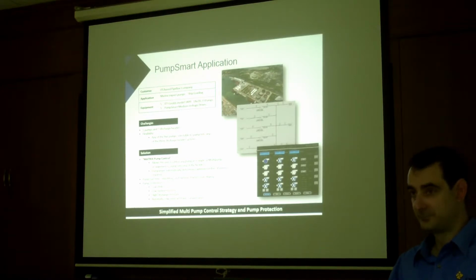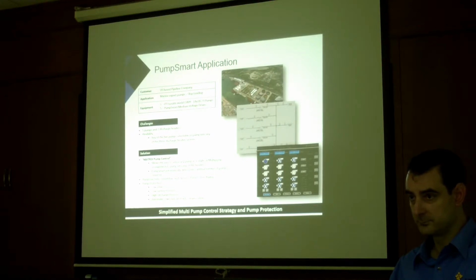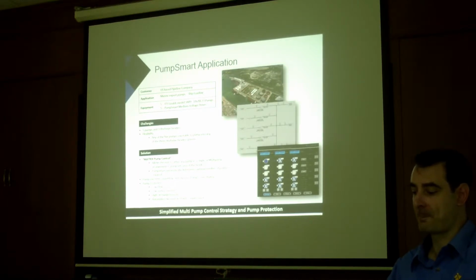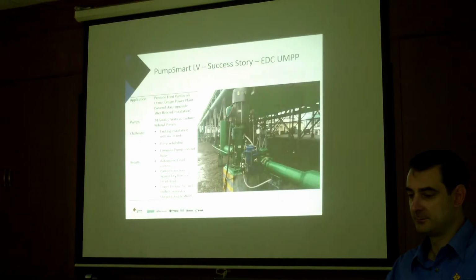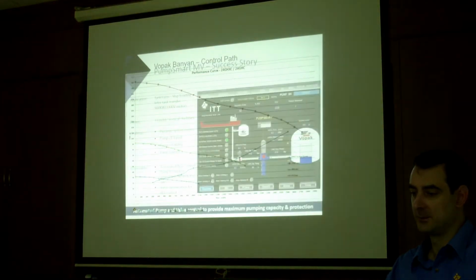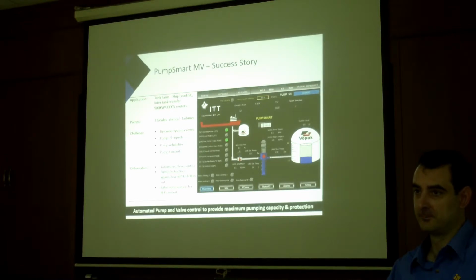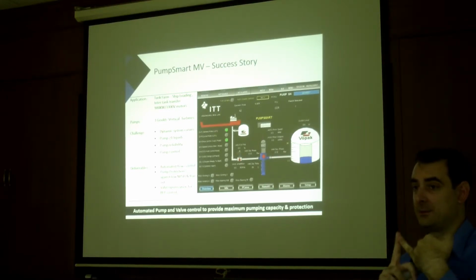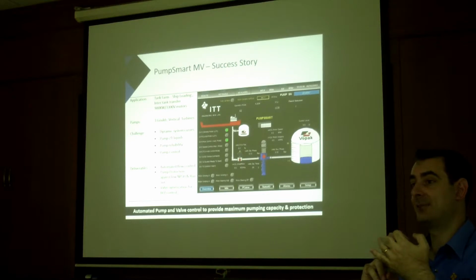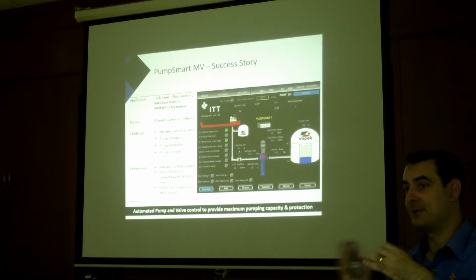Okay. Actually, I have one case for a fuel pipeline company, but they do the oil terminal also, and they use a pump for the ethanol and mix with the gasoline, and then they move the tank from near to far. So the pipe is fixed. So the problem is about NPSH. So I recommend to use this one to them. So there's ways we can automate, do it automatically. Yes, yes. But there's also ways that if they don't want to spend that much, we can help them do it manually, to fix the pressure.